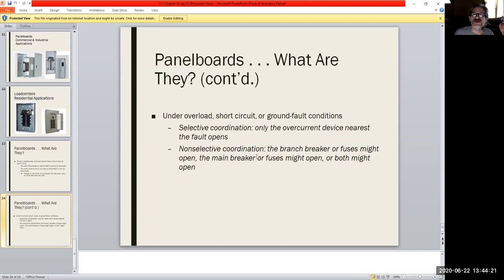Now, non-selective coordination, that happens. It does happen. When you have non-selective, the branch breaker or fuses might open, the main breaker or fuses might open, or both might open. And it's because things are mismatched. They're not being ideally utilized. Sometimes it all depends on the current pull and whatnot. I have seen it where the main breaker has tripped as well as the branch breakers. They both hit their time limits at the same time, and they both open up.